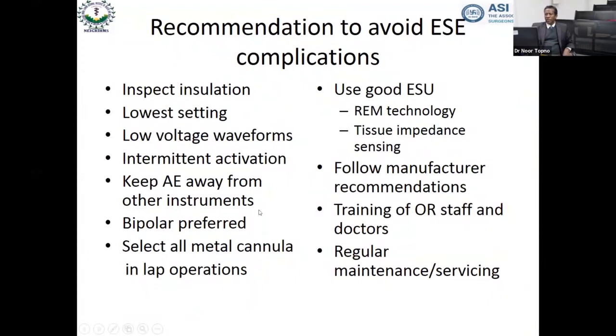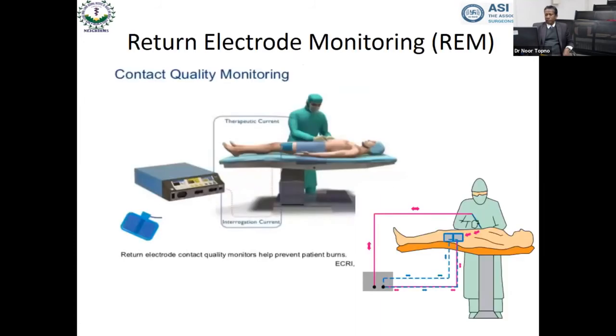These are some of the recommendations. Basically, inspect the insulation, use a low setting, low voltage waveforms, intermittent activation, and keep away from other instruments. Bipolar is always preferred. In laparoscopic instruments, always use all-metal cannulas. Of course, having a good ESU unit is always preferable. Now, what are the newer technologies?